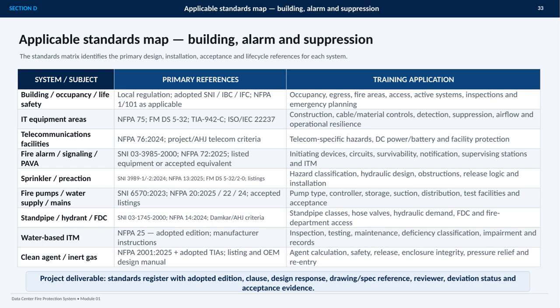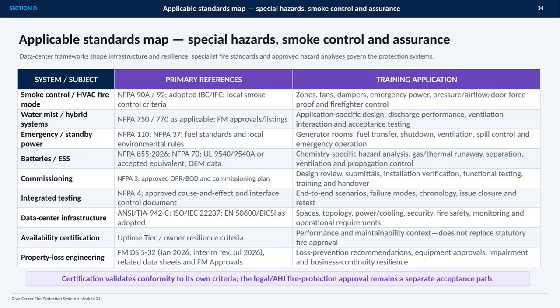The key project output is the standards register, with adopted editions, clauses, design responses, drawing and specification references, reviewers, deviation status, and acceptance evidence. This standards map connects each major data center fire protection subject with its primary references and its practical training application. The important point is that no single standard governs the entire facility. Smoke control and HVAC fire mode draw on NFPA 90A and 92, adopted building and fire codes and local criteria, with attention to fans, dampers, emergency power, pressure, airflow, and firefighter controls.